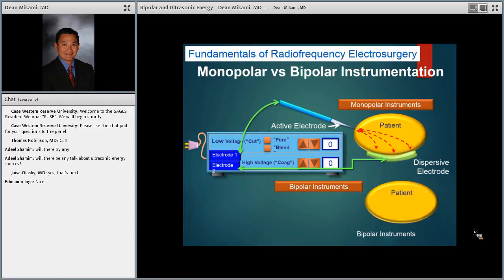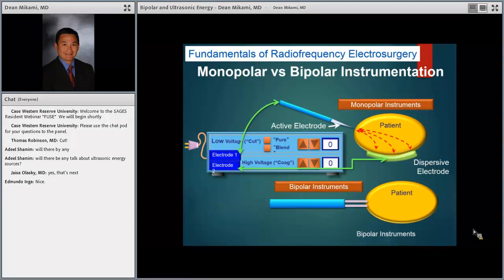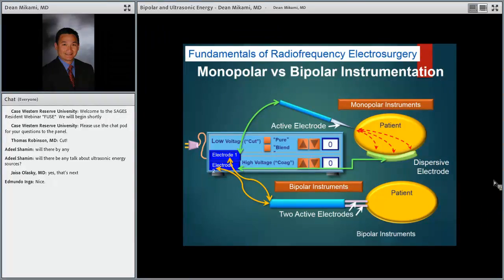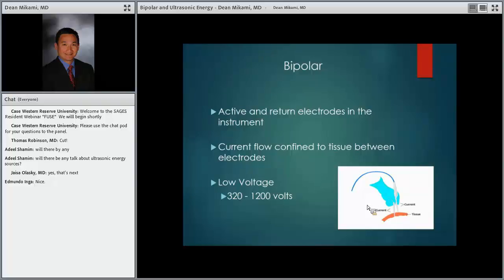Same thing with bipolar. In bipolar, you have the active electrode and the dispersive electrode actually right in the tips there, and you have your effect right between the jaws of the bipolar instrument. So in bipolar mode, the active and return electrodes are in the instrument itself. Current is confined to tissue between the electrodes, and it uses a low voltage, kind of in the cut waveform, to have its end effect on the tissue between that.